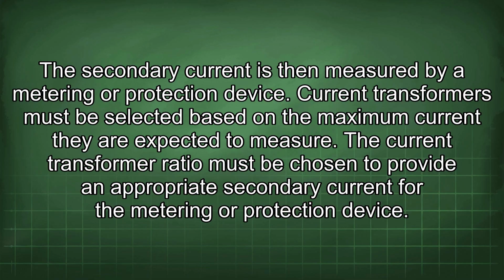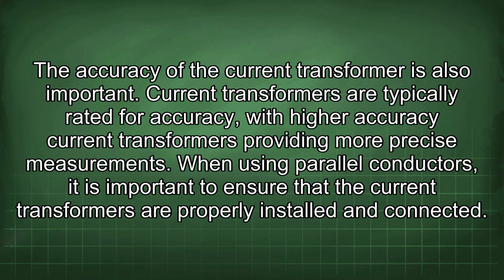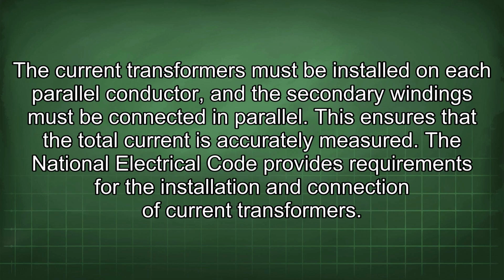Current transformers must be selected based on the maximum current they are expected to measure. The current transformer ratio must be chosen to provide an appropriate secondary current for the metering or protection device. The accuracy of the current transformer is also important. Current transformers are typically rated for accuracy, with higher accuracy current transformers providing more precise measurements. When using parallel conductors, it is important to ensure that the current transformers are properly installed and connected. The current transformers must be installed on each parallel conductor, and the secondary windings must be connected in parallel. This ensures that the total current is accurately measured. The National Electrical Code provides requirements for the installation and connection of current transformers.